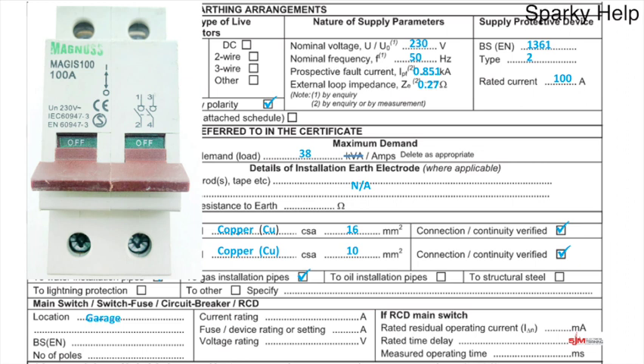The BS EN number we can see on the front, it's 60947-3. It's a fairly standard rating for switch disconnectors. How many poles? Well, there are 2 poles, and that's what you'd expect for a single phase installation. So 2 poles goes in there. Moving over to current rating, and we can see the current rating is 100 amp. Now, everything we tend to put on these sheets is there for a reason.